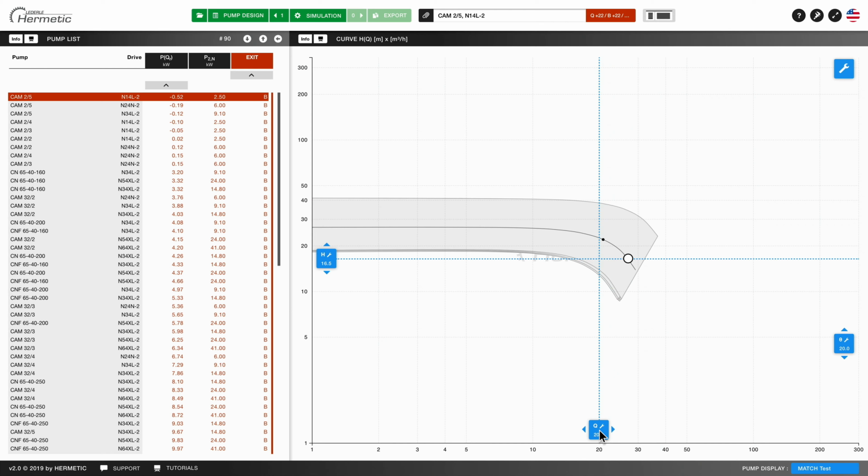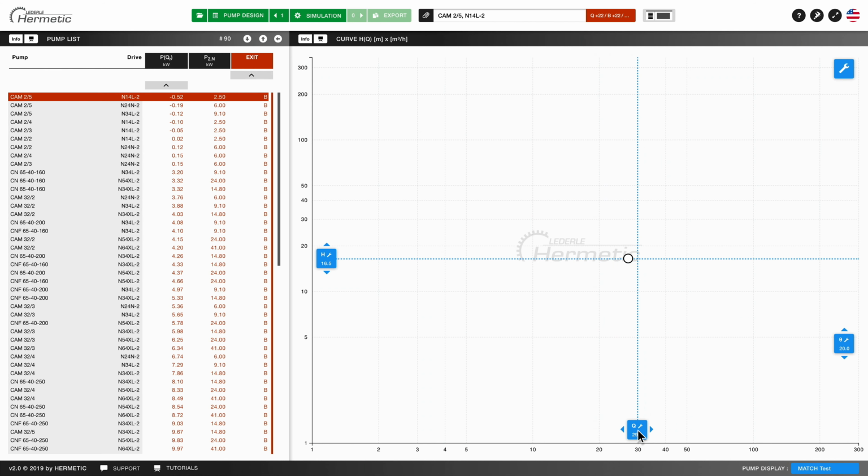We immediately get feedback in form of gray curves, which represent the subset of all formerly red pumps that match our probe settings. They are not yet simulated and approved, but pre-calculated approximations of what a revised simulation will probably confirm for our adjusted parameters. As an example, we want to assume that our tolerated volume flow minimum is 25 cubic meters per hour. Let's find out if we can find a match within our constraints.